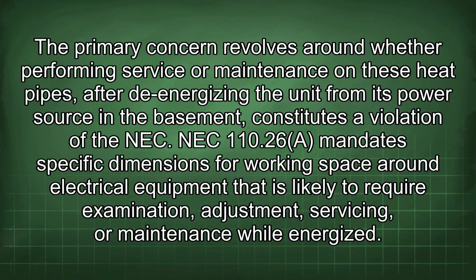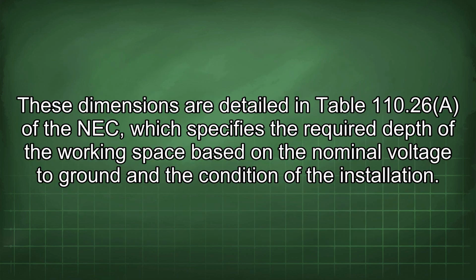NEC 110.26 mandates specific dimensions for working space around electrical equipment that is likely to require examination, adjustment, servicing, or maintenance while energized. These dimensions are detailed in Table 110.26 of the NEC, which specifies the required depth of the working space based on the nominal voltage to ground and the condition of the installation.